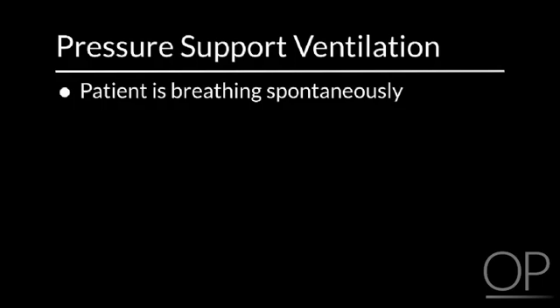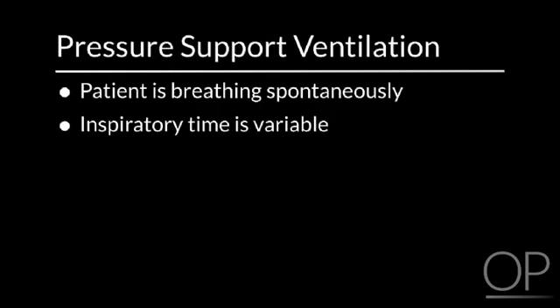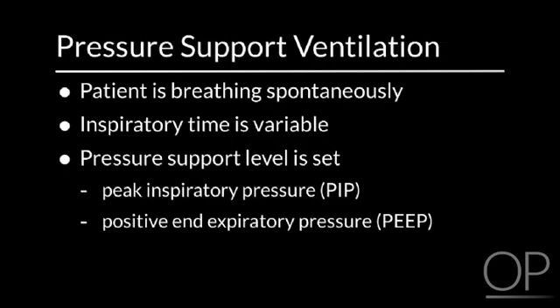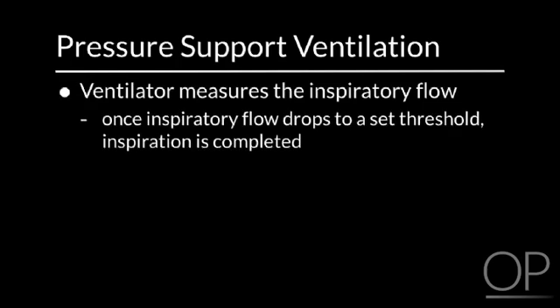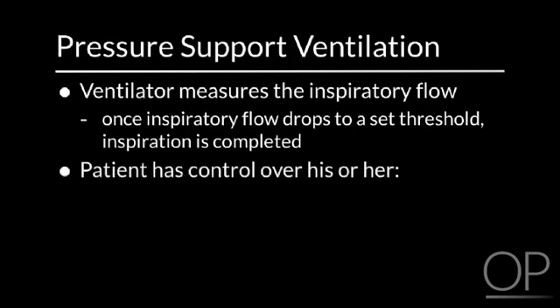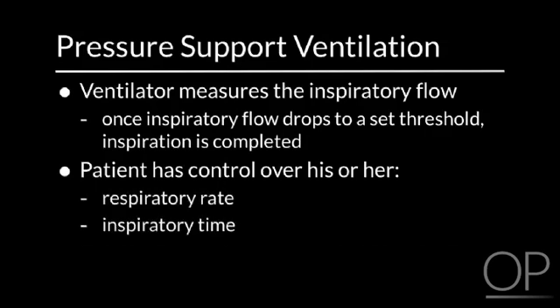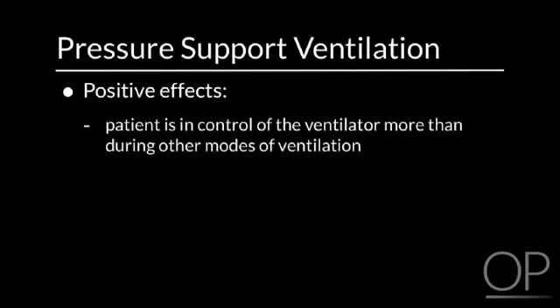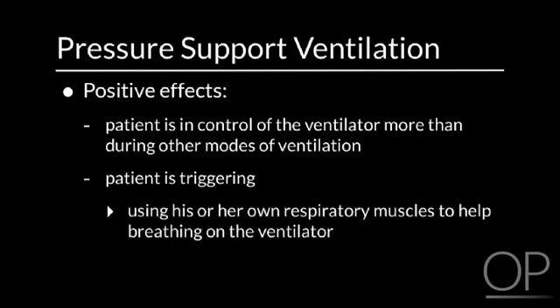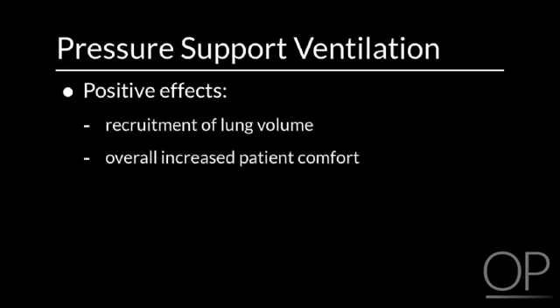Pressure support is a mode of ventilation that is widely used now. The patient is breathing spontaneously and the inspiratory time is variable. While on pressure support, there is a pressure support level set with a peak pressure and a positive end-expiratory pressure, but the inspiratory time is determined by the patient. The ventilator measures the inspiratory flow, and once that drops to a certain number, inspiration is regarded as completed. So the patient has control over both respiratory rate and inspiratory time. In comparison, in SIMV the patient can trigger, but once triggered, the inspiratory time is set. Pressure support means the patient uses his own respiratory muscles, which can lead to recruitment of lung volume and increased patient comfort.